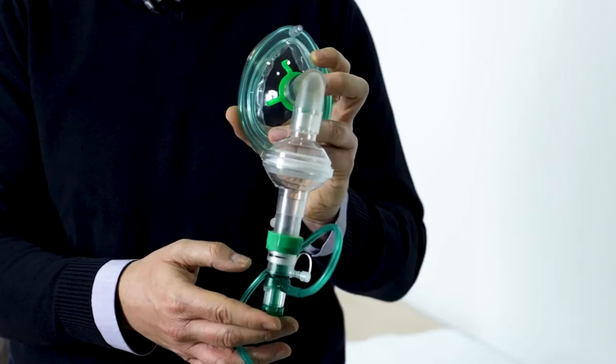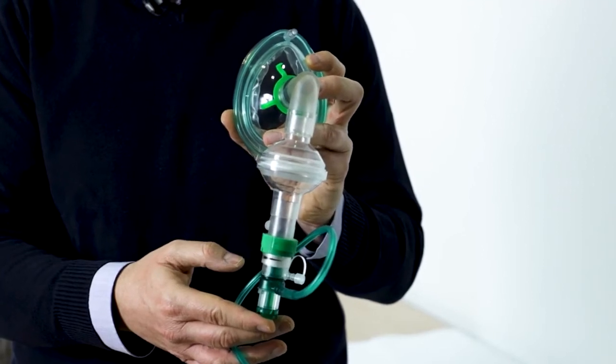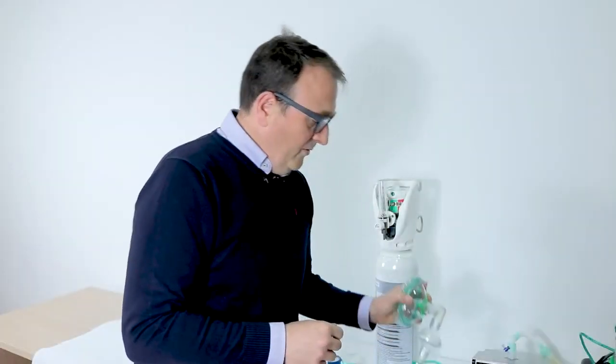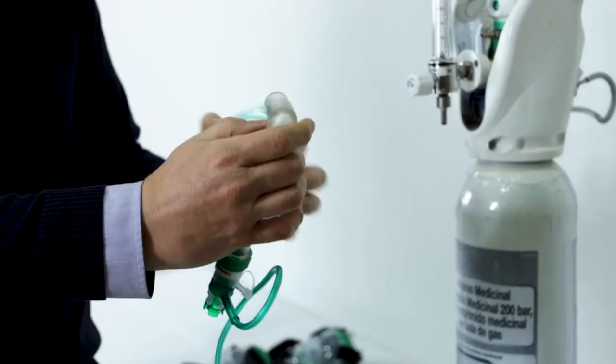After showing how to assemble the filter to a CPAP system to make the system safer in the case of treatment of patients with respiratory infections, I'm going to show you how to interconnect a T-piece for nebulizing therapy. This is very important because sometimes patients need this type of therapy, and it's really important to decrease the spread of infection particles. First of all, we need to disconnect the elbow here.